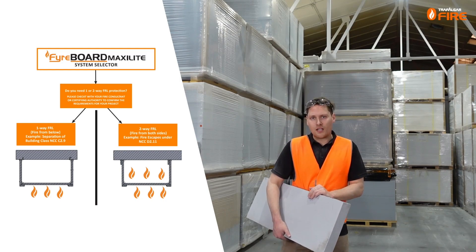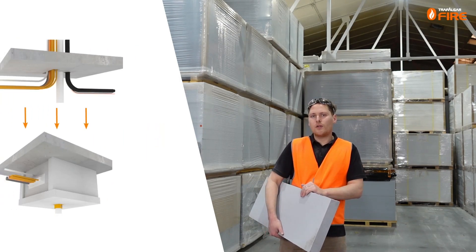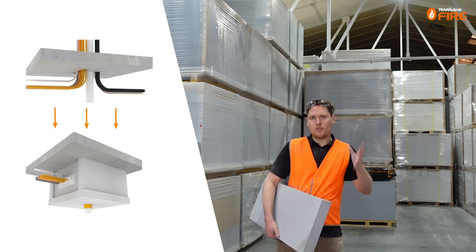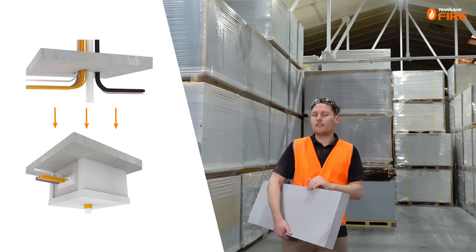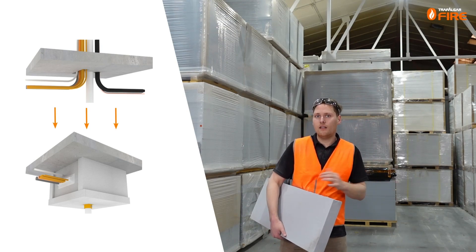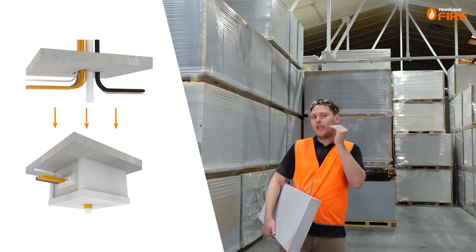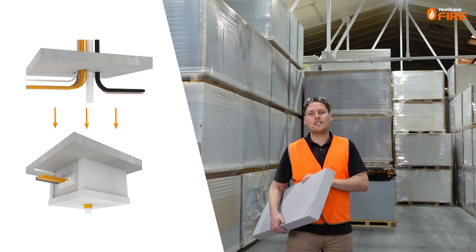There is one other type of Maxilite construction — what we call a penetration box-out. When you have services penetrating through a slab, you can use our 40mm Maxilite board to box in around the underside of those services if you don't have access to the top side, treating the penetration by moving it down underneath the slab where you can fit it. When a penetration comes out of any of the bulkheads, they all need to be thickened up to at least 60 millimeters.